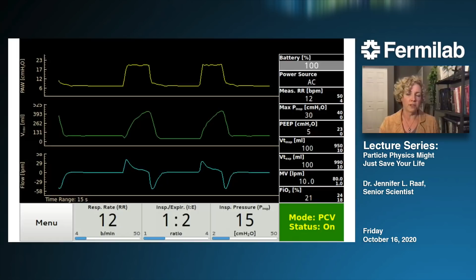And the waveforms are showing you various things that are measured at the patient. So the top one's showing the patient airway pressure. The second one is the volume of air, and the bottom one shows you the flow rate in liters per minute. That column of things along the right side are measured values. And the tiny numbers on the far right of those boxes are the minimum and maximum values for the alarms. So if any measured value goes outside of its alarm range, then the box containing that number would turn red and an audible alarm goes off, as well as a very bright LED that's on the front of the ventilator enclosure.